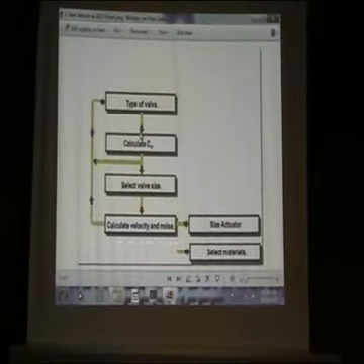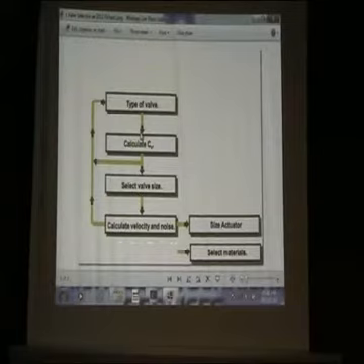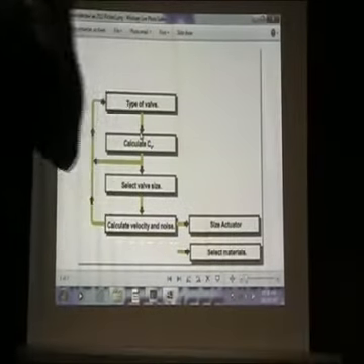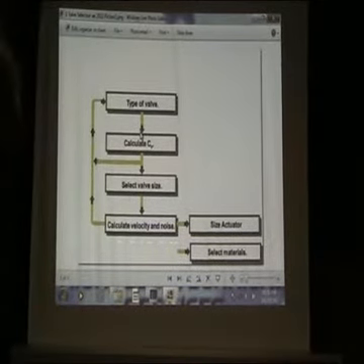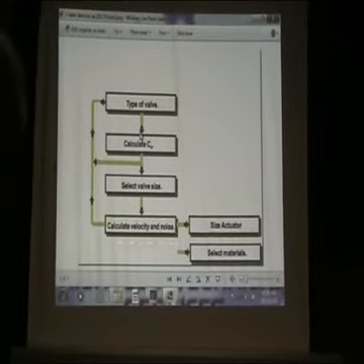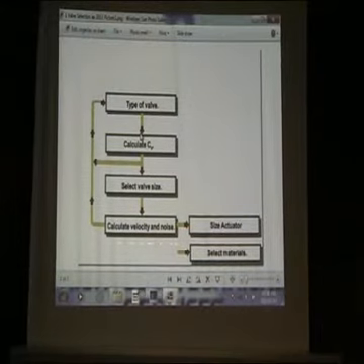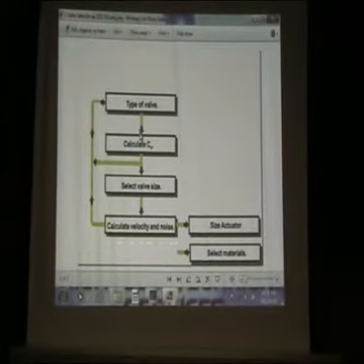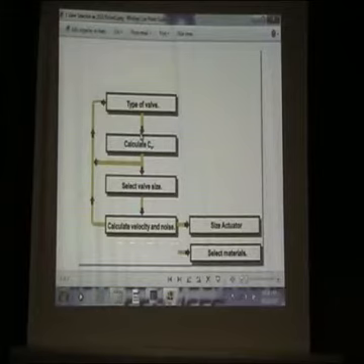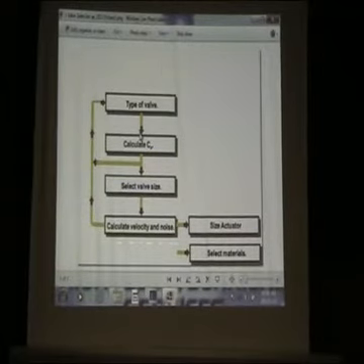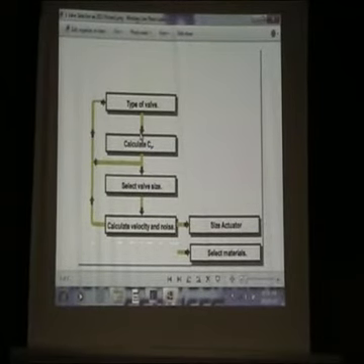Next thing, we said media. Remember temperature? You can't put this valve in on 300 degrees, because remember those rubbers can only take 80 degrees Celsius. And then flow. I'll mention the most important one last. Flow. Remember flow? You need to know how much flow needs to pass through this valve. If you don't know that, you've got a problem because you can't pass 100 cubic meters through a valve that can only handle 30 cubic meters. You understand? So it's an important thing. There's just 4 or 5 elements.